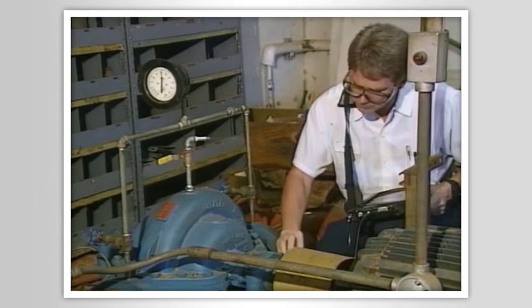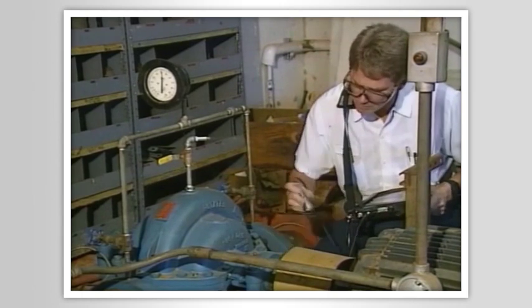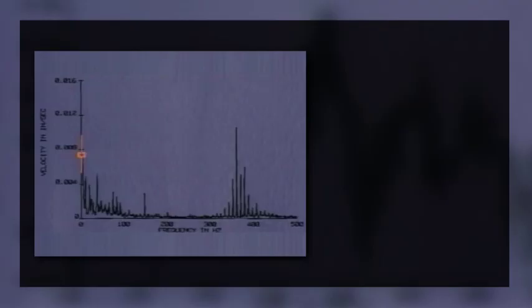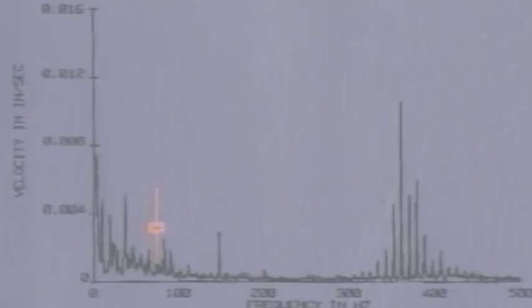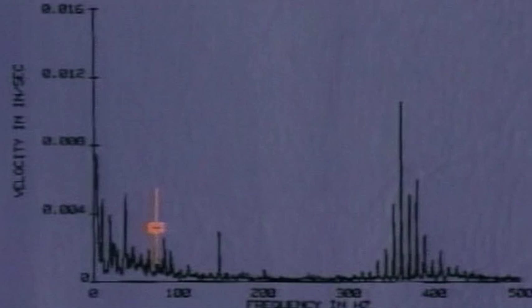Now let's look at a spectrum taken at the inboard bearing. The one-times is at a higher amplitude than in the previous spectrum, so there may in fact be a little shaft movement. But amplitude is still very low, and the one-times harmonics have disappeared. So the problem, if we can call it a problem, is very minor. The vane pass frequency is also at a low amplitude and does not generate harmonics.